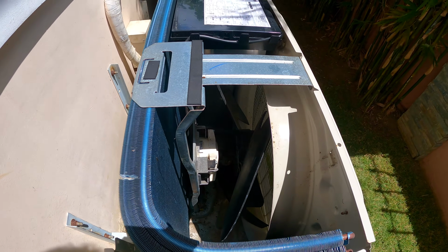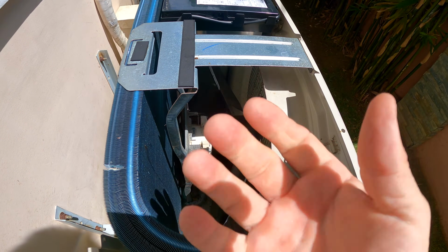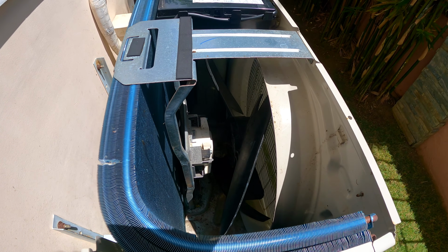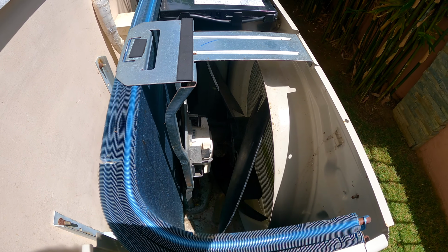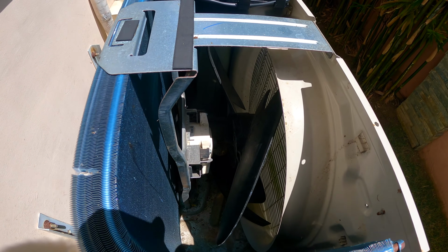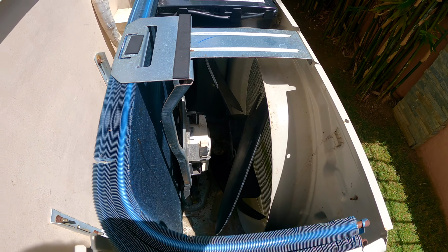Then I turned off all the power, and I felt the back of the motor, and it was extremely hot, like it burnt my finger when I touched it. It should not be like that. So there's possibly some coil wires on the inside of the motor that went bad. I don't know, but this is what I suspect is bad inside this unit.